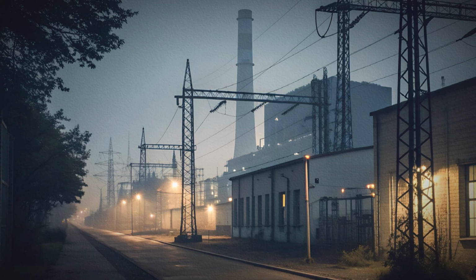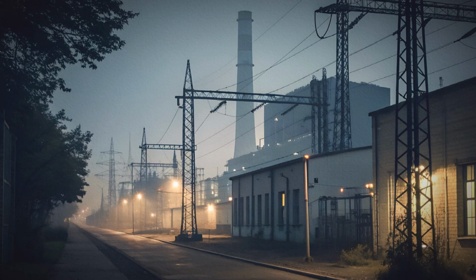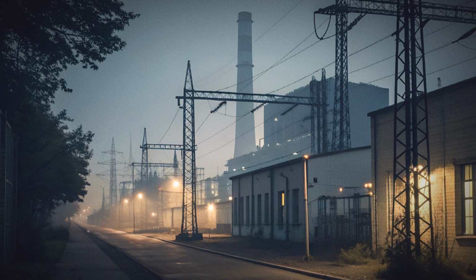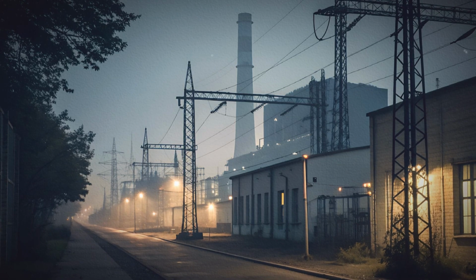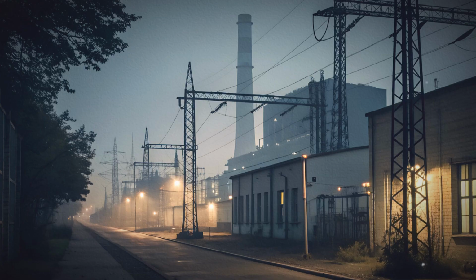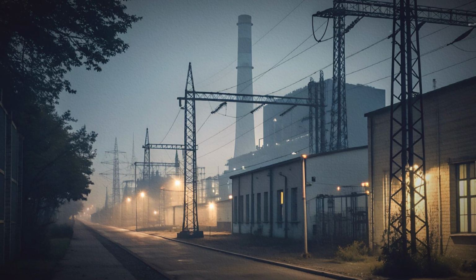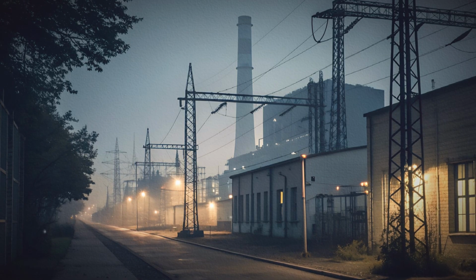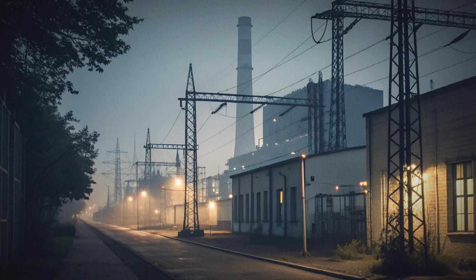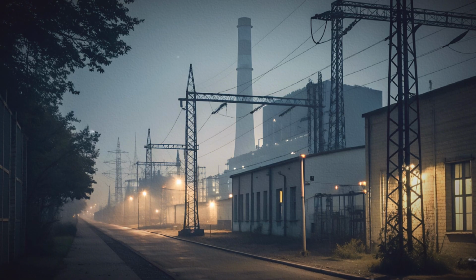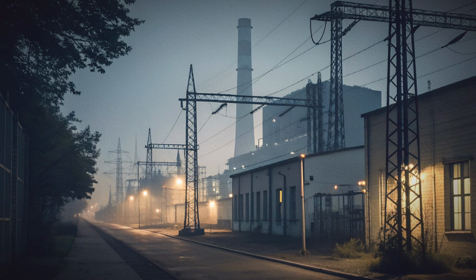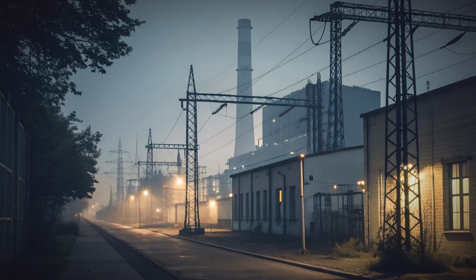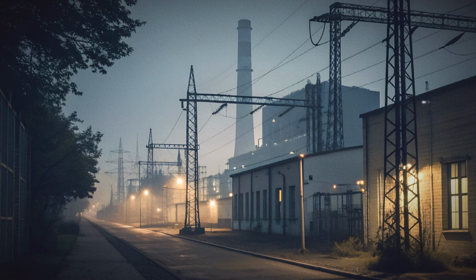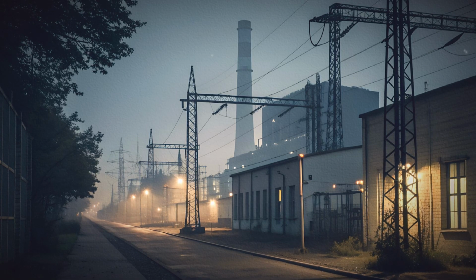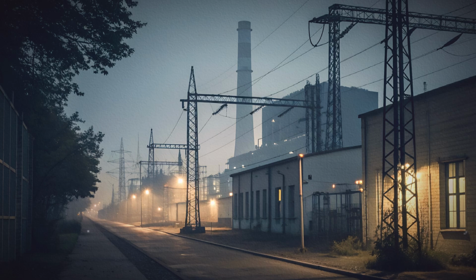Several generation sources operate in parallel on the same grid. Parallel operation means that multiple generators are electrically connected to the same network. They must share the same frequency. They must be synchronized in phase and voltage before connection. Synchronization ensures that alternating waveforms align closely enough to avoid current surges when a connection is made.